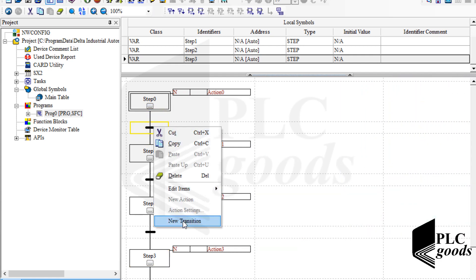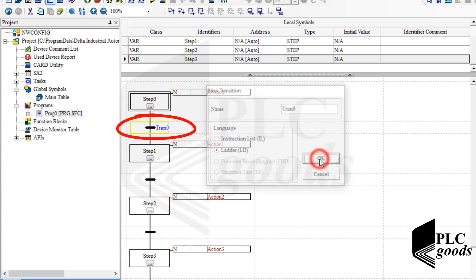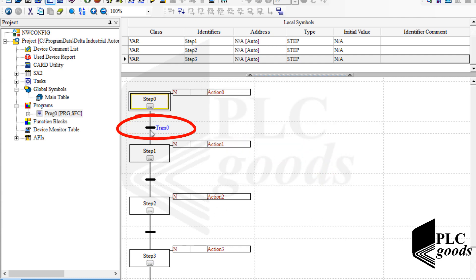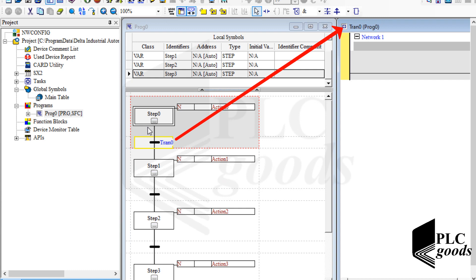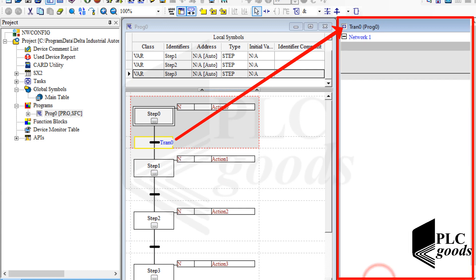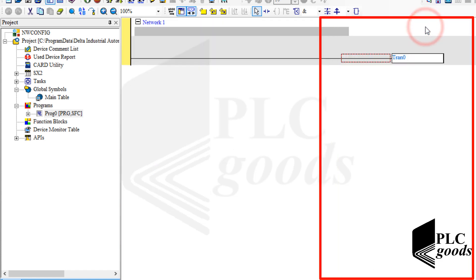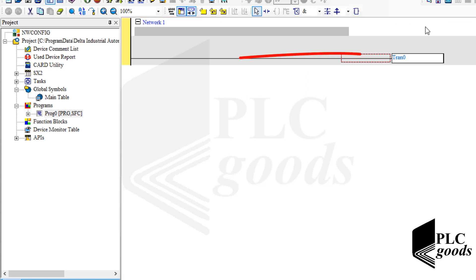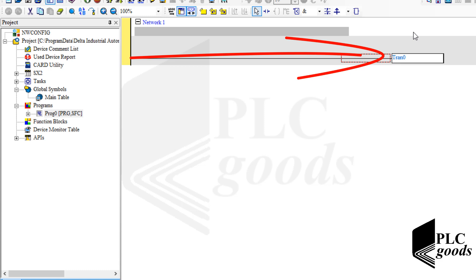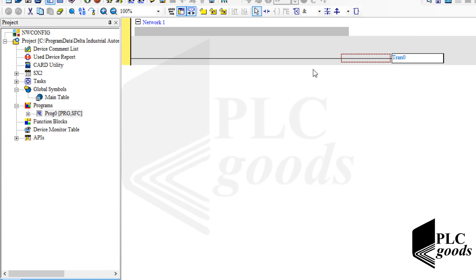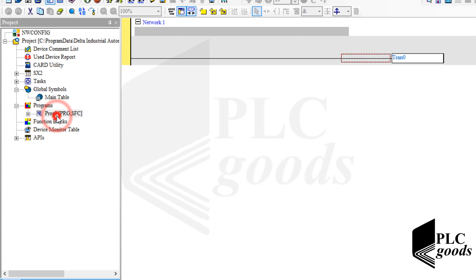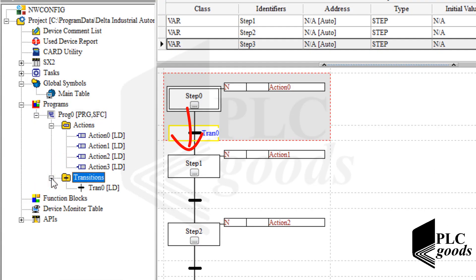Now let's create a transition. Transitions can be added between two steps and include conditions that determine when the PLC must exit from the current step and go to the next one. Let's open the created transition. The transition coil is located on the right side; we must write the transition condition on the left side. By default the transition coil is activated, and since I don't want to add any condition to this first transition, the PLC will exit from the first step immediately.